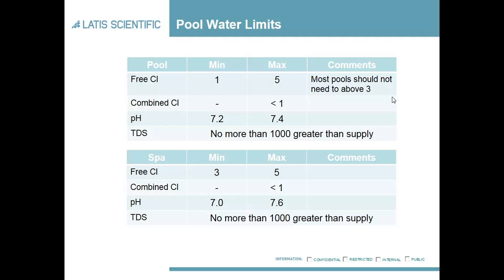Once combined chlorine starts getting higher than one it's obviously a slight concern. The pH levels you want between 7.2 to 7.4. And the total dissolved solids or TDS, you don't want to be more than a thousand greater than the incoming supply. Depending on whereabouts you are in the country that will vary quite significantly, generally being higher in the southeast and lower in the north of England.